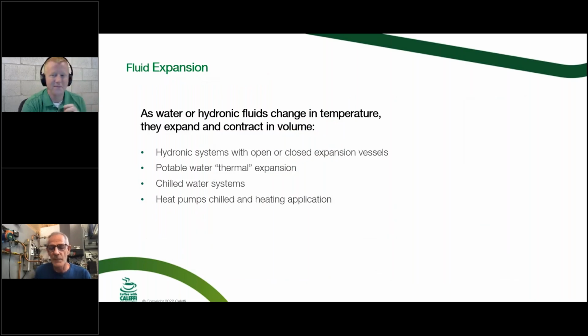Yeah, so basically what we're going to talk about is we heat up a fluid, water, or maybe a glycol mix. It's going to expand, and the opposite happens if we chill down a fluid, it's going to contract. So we need to be able in a closed sealed system be able to accommodate that somehow, so we don't pop relief valves. On the other side, if we go into a negative pressure condition, we can cavitate our pump. So we're going to look at the vessels that can be used to do that. We're going to look at a completely open system like they still do in places with just a bucket up in your attic that's insulated as an open system, and the pros and cons of all these different types of tanks, and how to size them, and troubleshooting a little bit also.